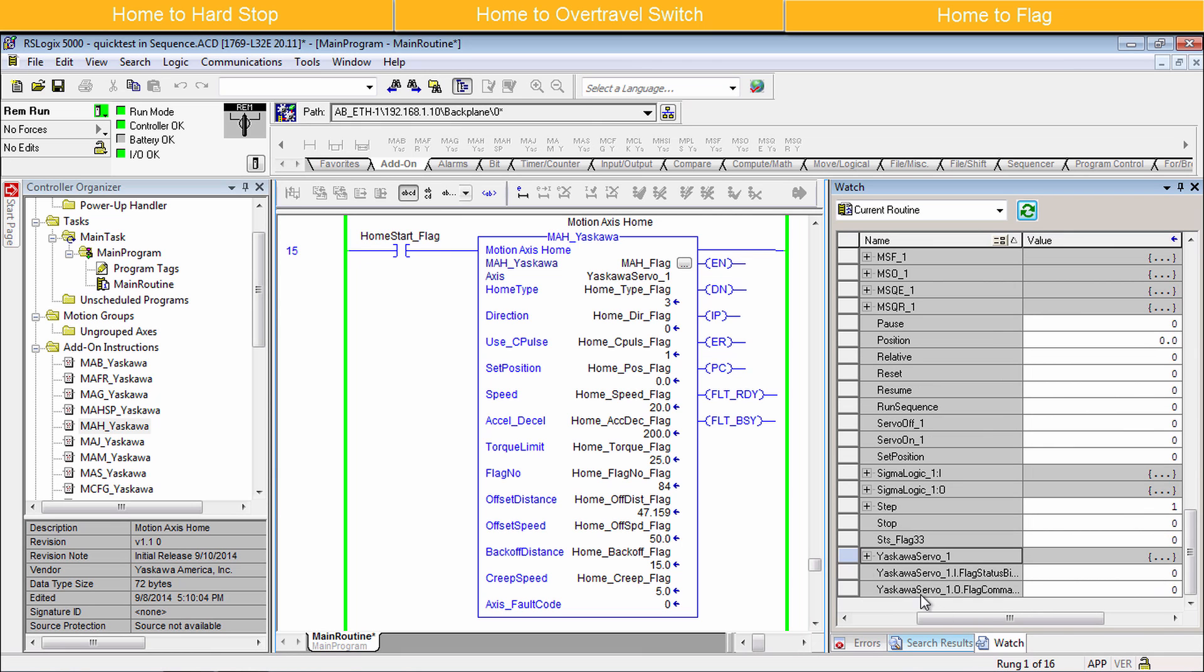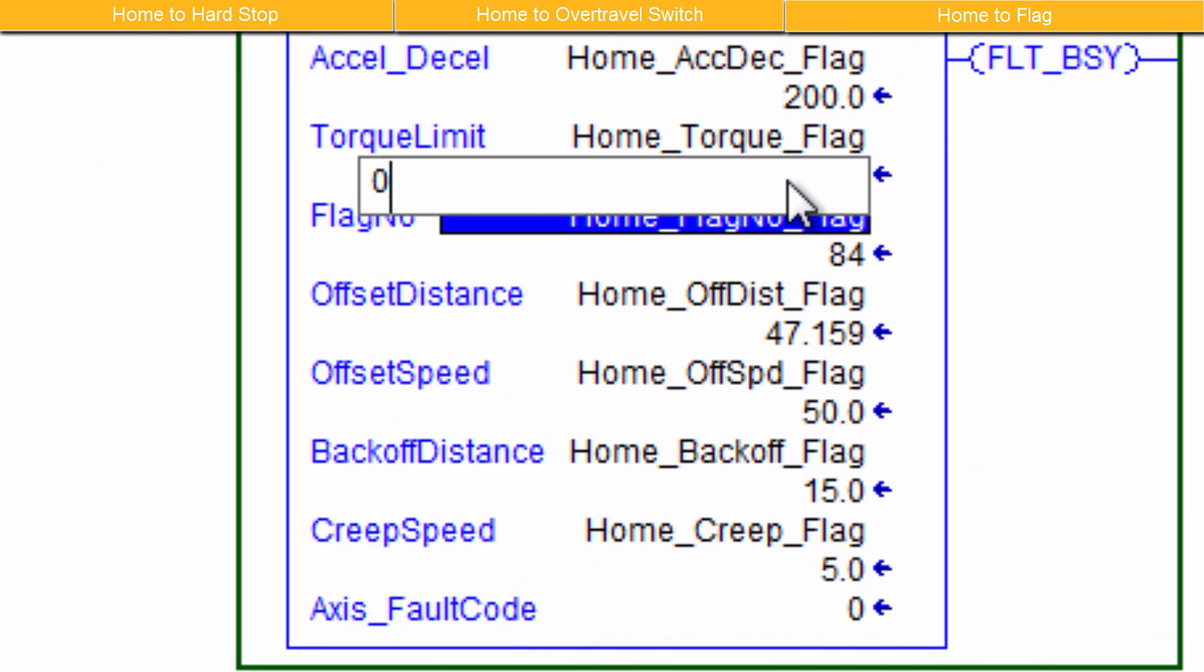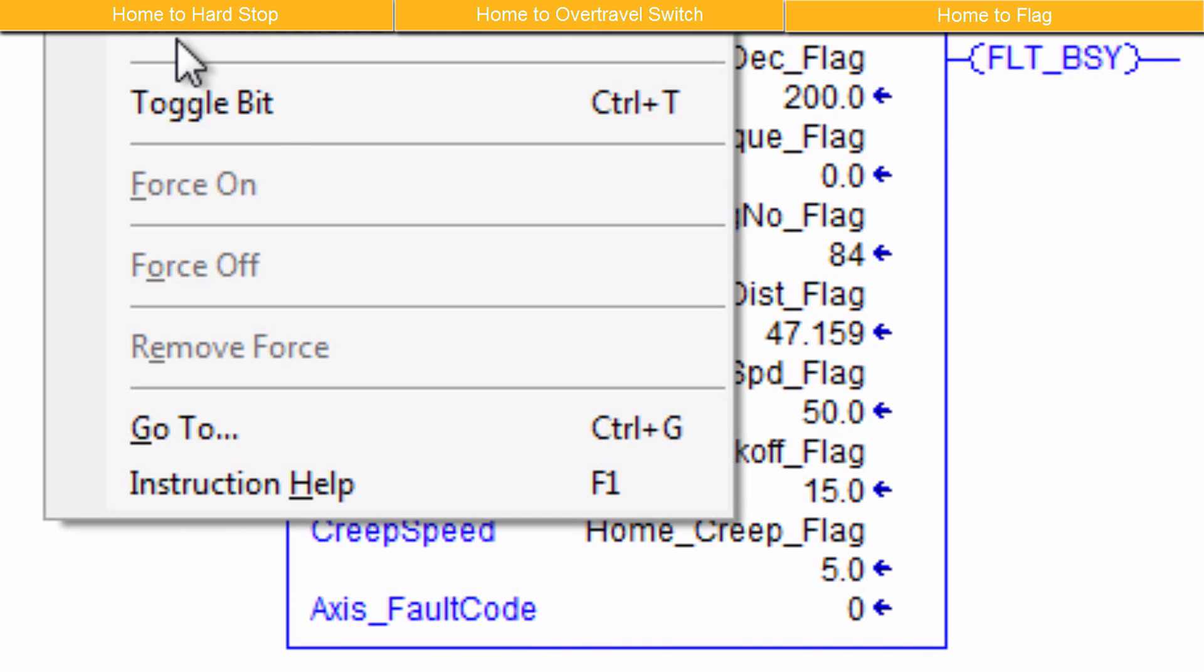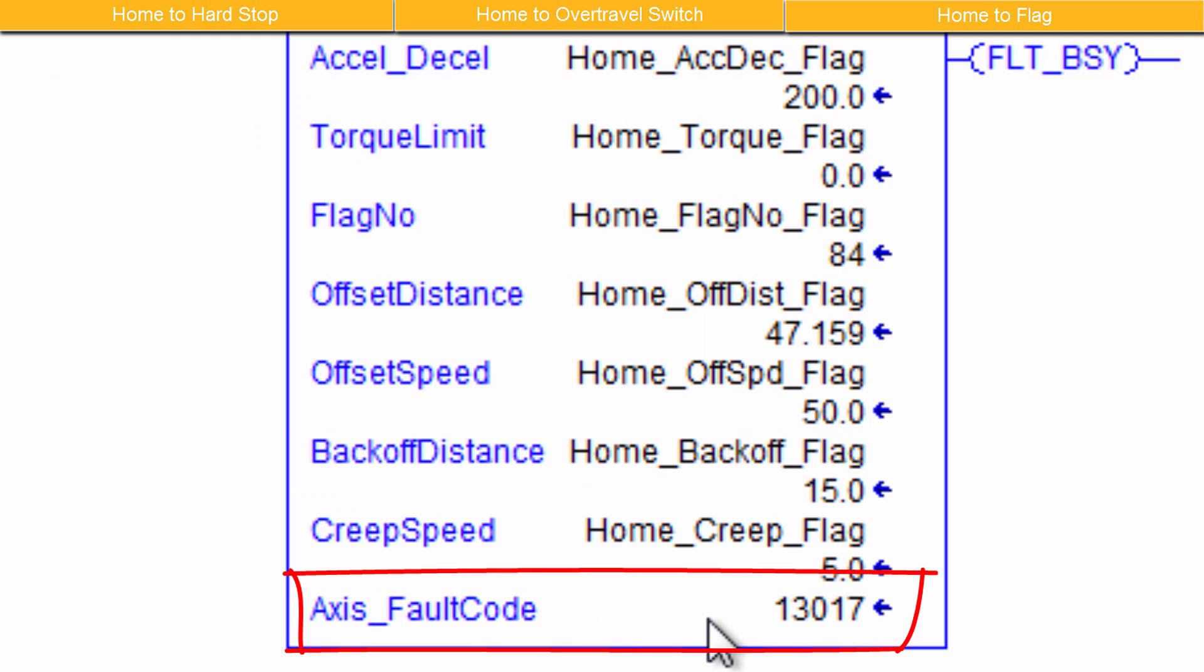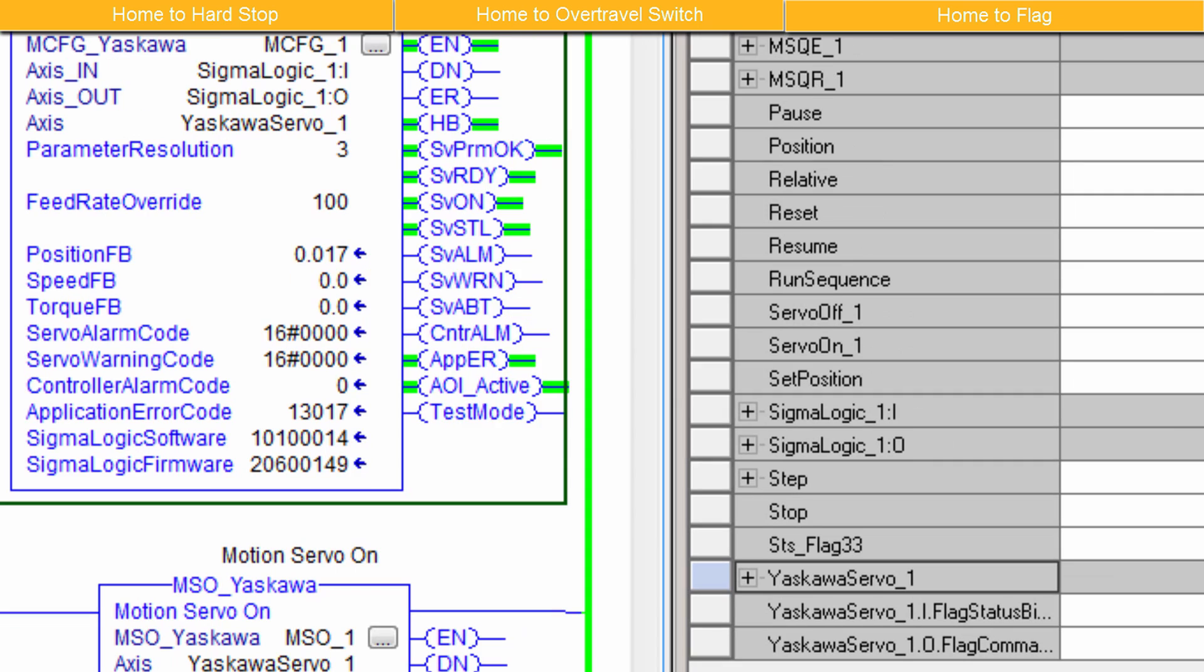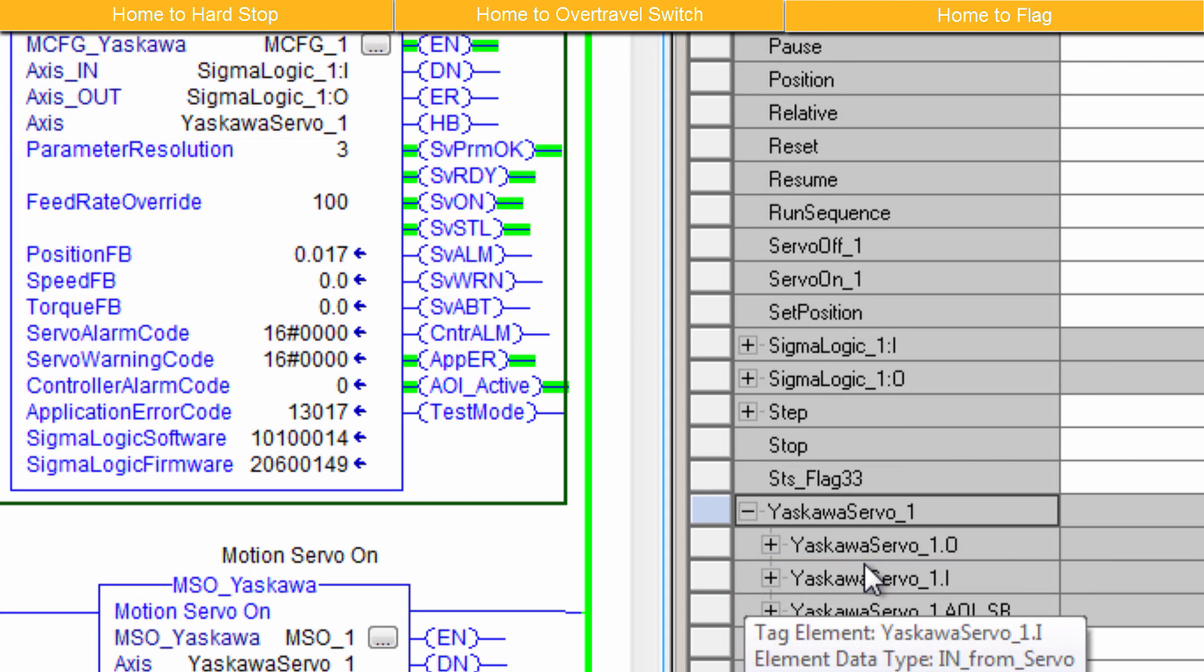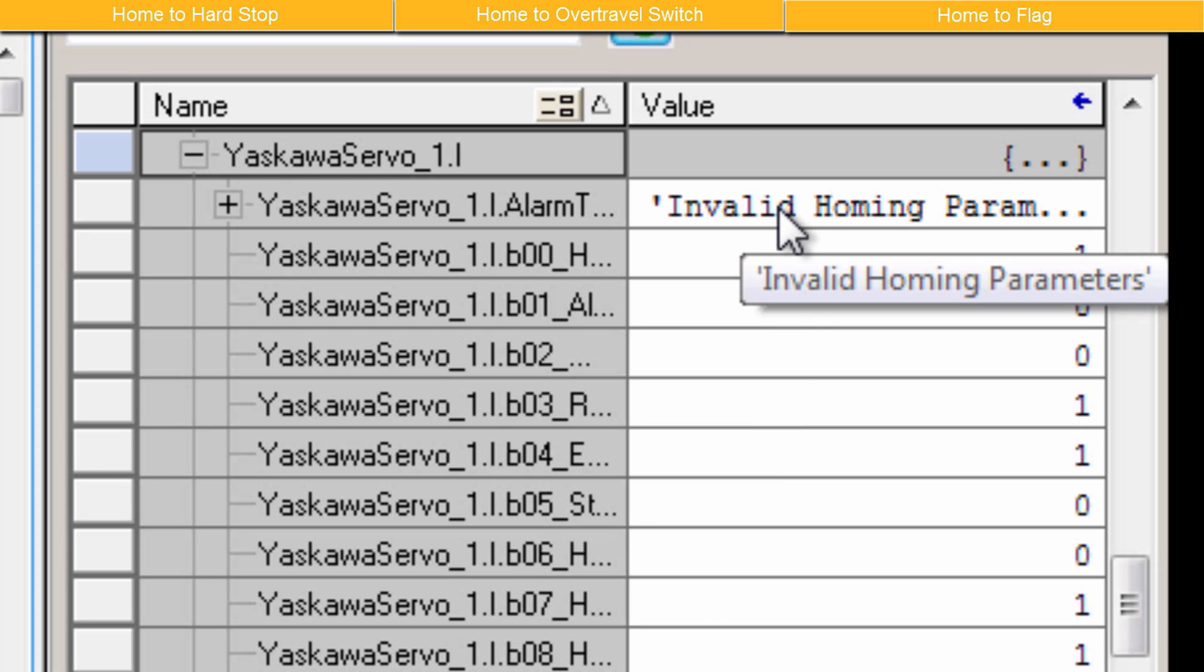During development of the homing routine, it is common to have invalid parameters. For example, here I've left the Torque Limit parameter at 0. An Axis Fault code 13017 appears in the instruction. The MCFG block also reports this application error code. To see a text description, monitor the Axis variable, which in this example is Yaskawa Servo 1. Expand to find element i for inputs, and expand to see alarm text. And here it reads invalid homing parameter.